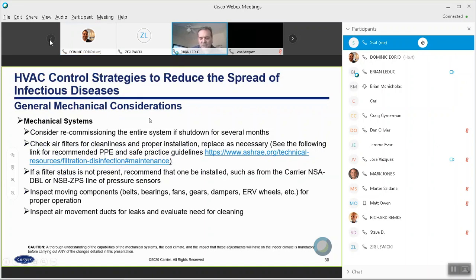Okay, so these are bits of guidance we got from the rooftop guys. Again, they emphasize the benefit of potentially recommissioning your equipment if it has been shut down for several months, an evaluation of the filters for cleanliness, proper installation. One thing that I didn't mention earlier, if you're replacing your filters and you're increasing their effectiveness in attempting to limit or trap virus, ASHRAE is recommending that whoever's doing the filter replacement do so with personal protective equipment.